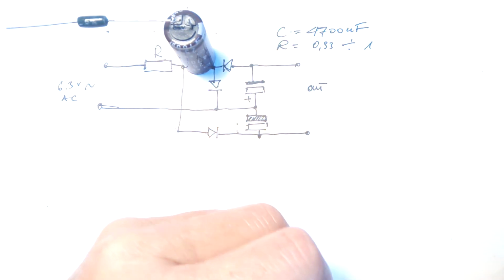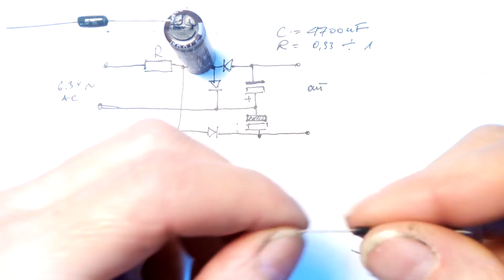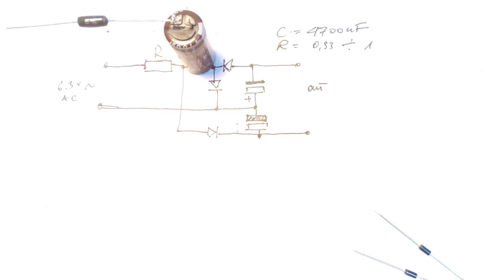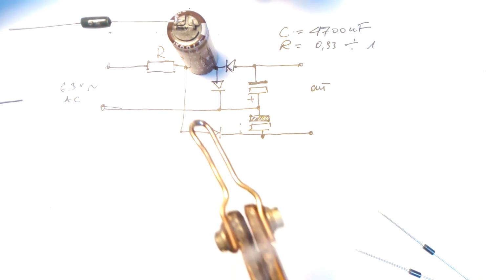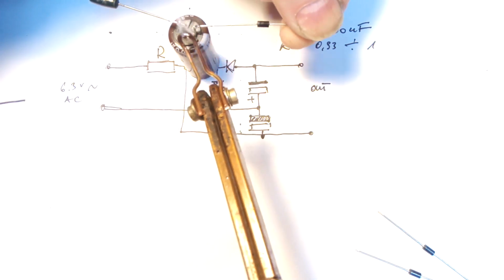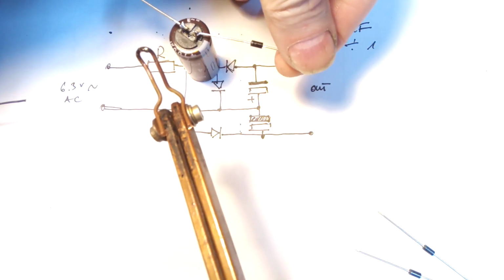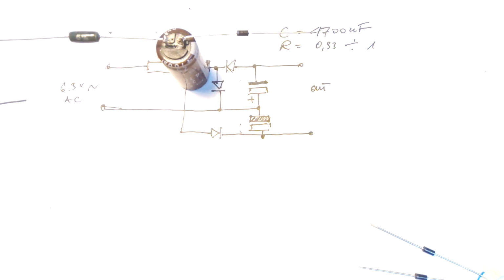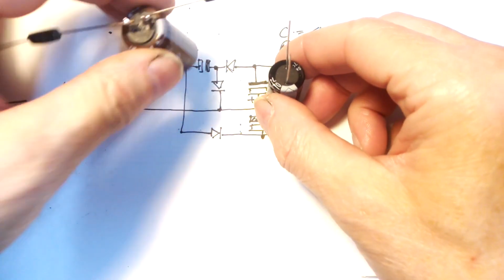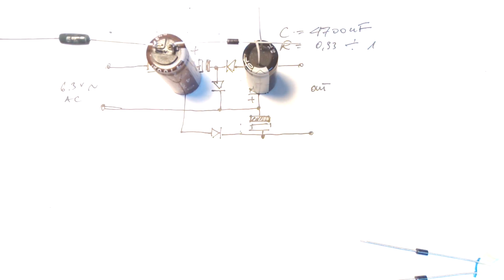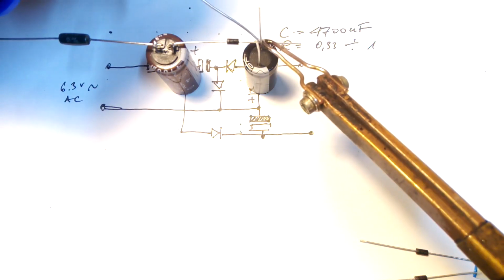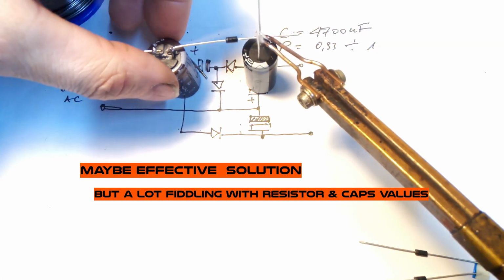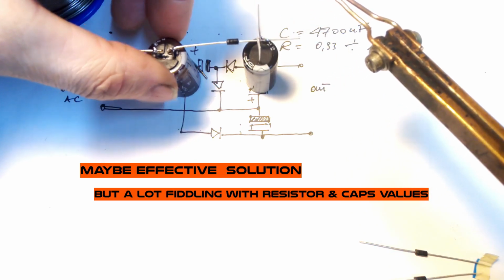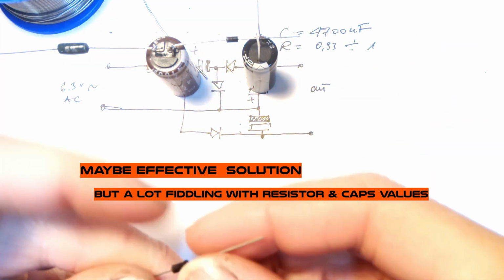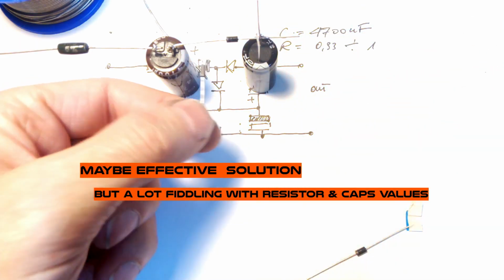The solutions are simply and effective if we have enough capacity of volume of power in the transformer winding. It's not totally dependent on the size. The most important thing is the size of the winding, the thickness of the wire, because if the wire is a bit thicker we can overload the transformer a bit longer and it will work. It means we're working in the same style, with testing in the end.